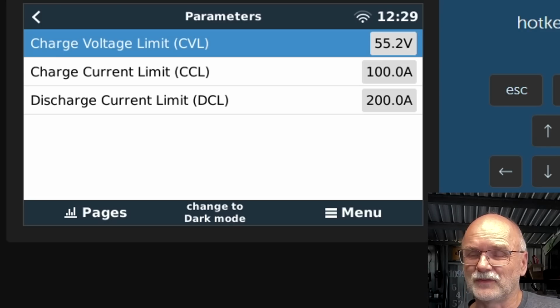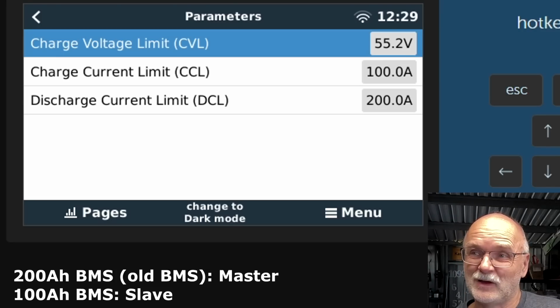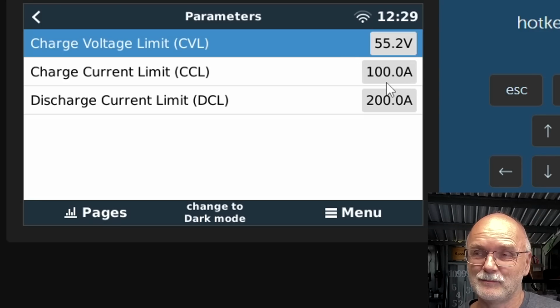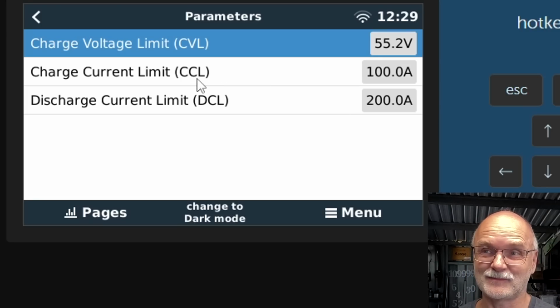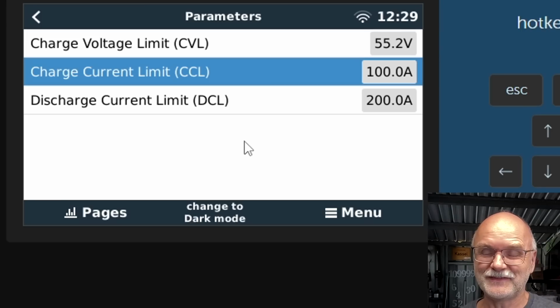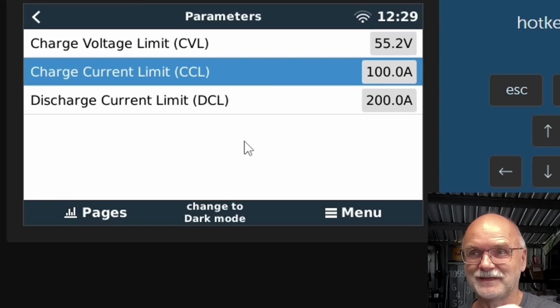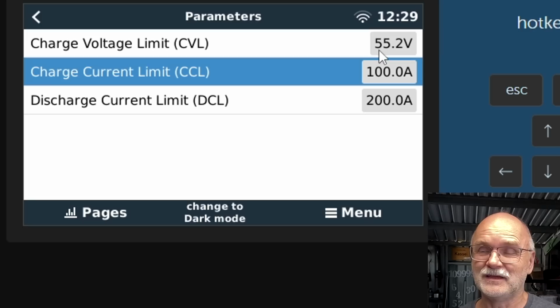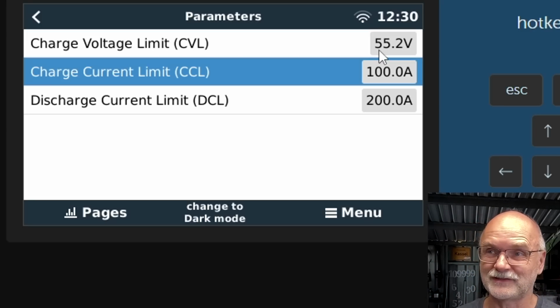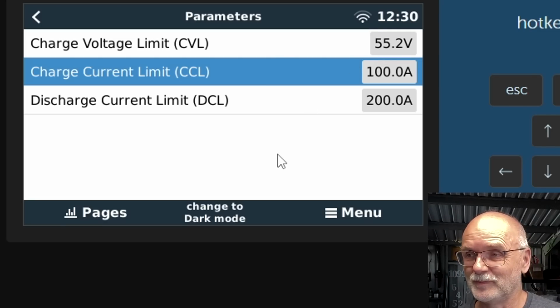Right. So this is the old 230 ampere hour battery now with the old Pace BMS as the master, and the 100 ampere hour Pace BMS at the top is the slave. And we have the exact same result here. Both BMSs sit on 100 amp, but they're reporting only half of that as the maximum charge current to your inverter. While the discharge current between the BMS is added up and then reported as a sum to your inverter. So 100 plus 100 makes 200. And again here, the full charge voltage is our CVL, our charge voltage limit, which makes total sense. So I'm not sure why they changed this in the new BMS software.